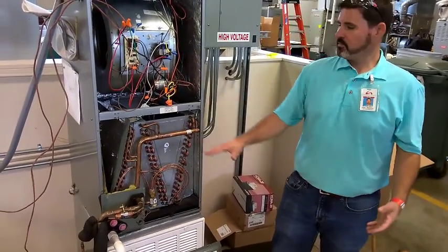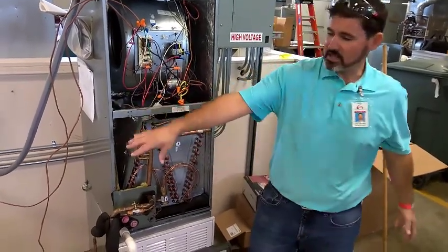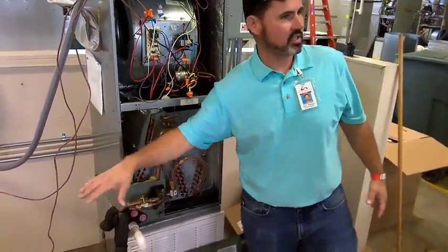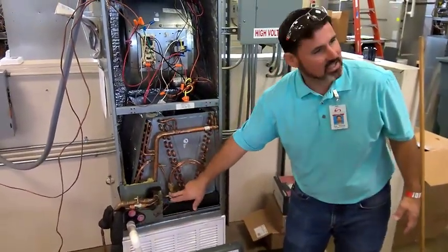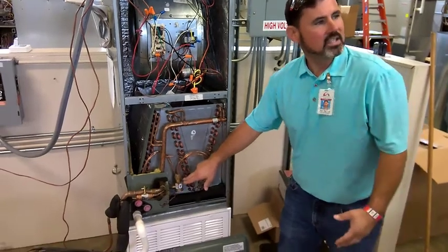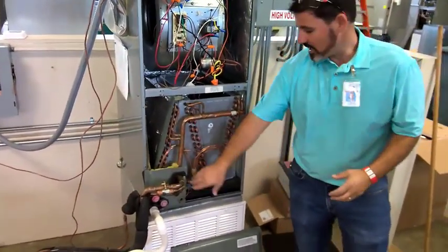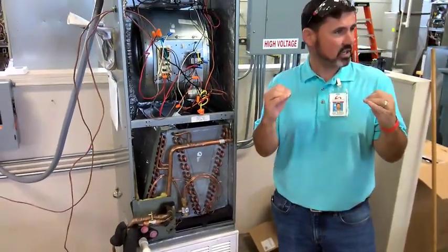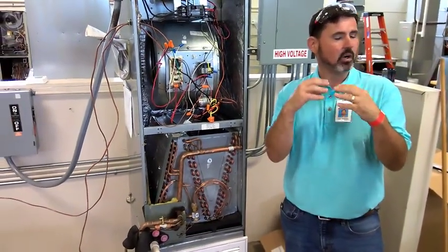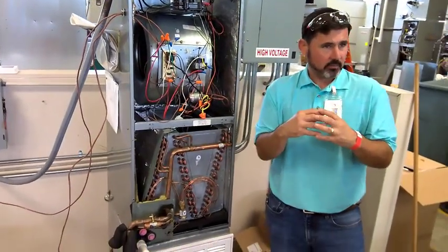All right? So once I've absorbed all the heat that I can, again, I told you about my superheat, my subcool, and my saturation. The same thing is happening here. I've got that subcooled refrigerant that hits that metering device. Once it hits it, it instantly flashes off some, so I start out automatically at that saturation point. Remember, I said saturation is the actual temperature where it's going from a liquid to a vapor, or a vapor back to a liquid. All right?